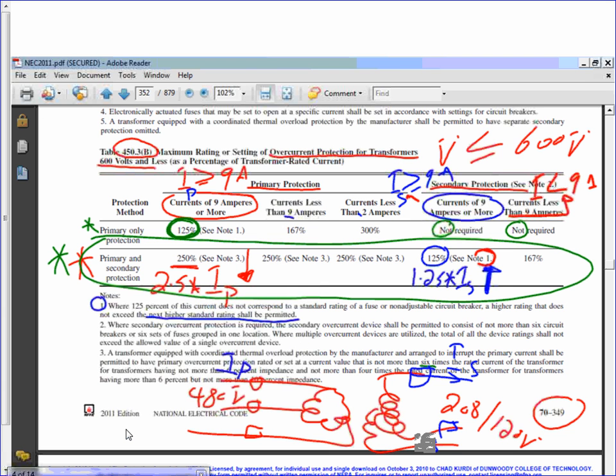You use this table, guys, if both the primary and the secondary are less than 600 volts. You use this table if your primary and secondary are less than 600 volts. Before I let go of this table, can you guys give me a thumbs up that we know how to use it? Yes? No? In between? Okay. So current less than 9 amps. There are 2 columns here. Current less than 9 amps is for smaller transformers, control type and what not. Typically, mostly going to be in the column that says current more than 9 amps.